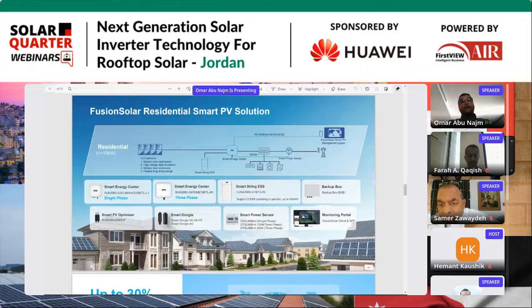As well, the smart power sensor is provided by Huawei for some projects that need zero export or limitation in the exporting system. You have to use the smart power sensor, which mainly gives commands back and forth between the inverter and the grid, giving you the needed energy as requested.